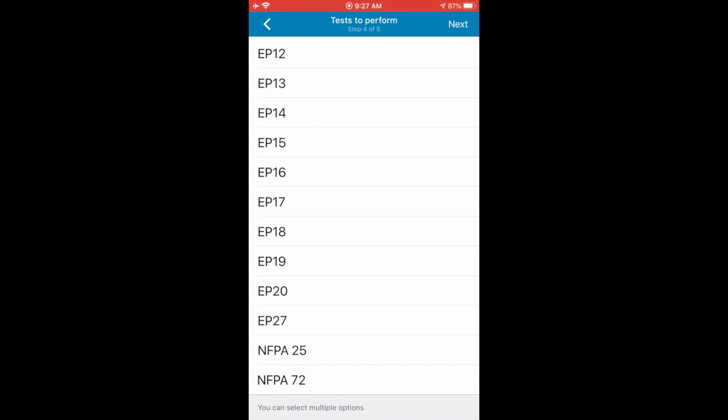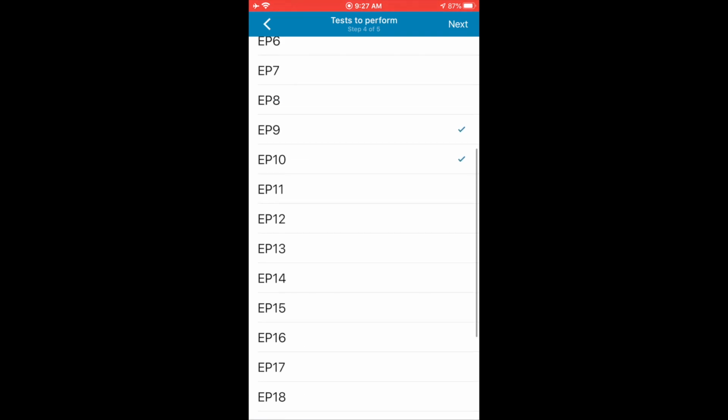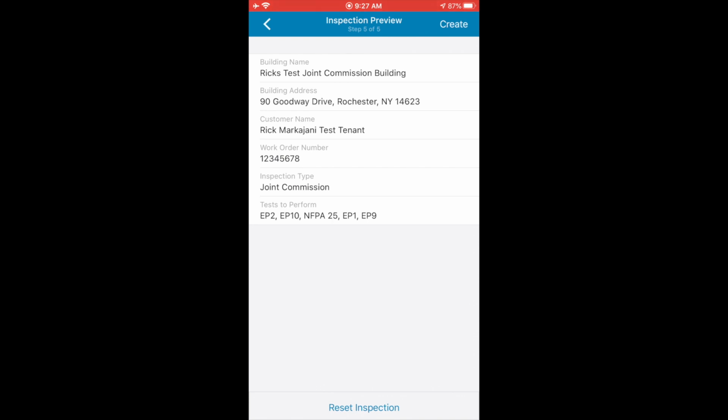But I am going to choose NFPA 25, which I will choose on every inspection that I'm doing in Joint Commission for sprinkler, no matter what EPs I'm choosing, because I do need my NFPA 25 questions. I'm going to select next at the top, and I'm going to verify that I have everything I need. I've got EP1 for my supervisories, EP2 for my flows and tampers, 9 for my main drain, and 10 for my fire department connection, as well as NFPA 25 for my non-EP questions. I'm happy with this. I'm going to select Create.